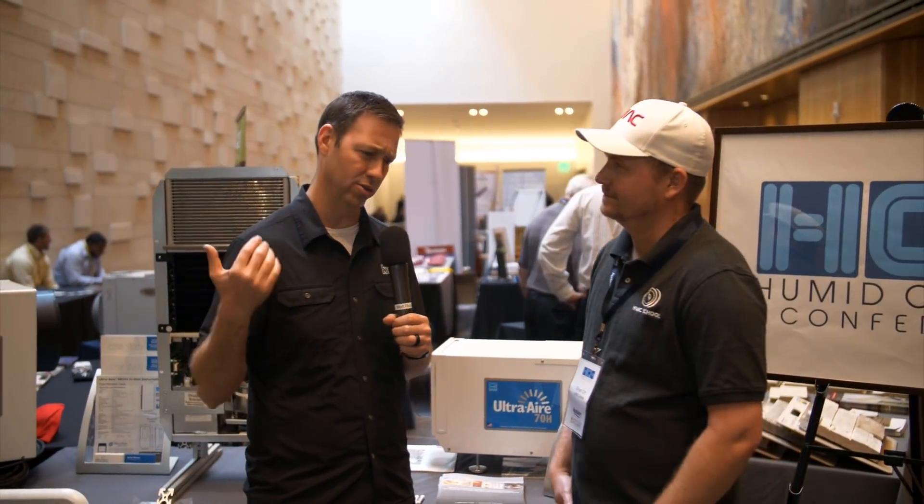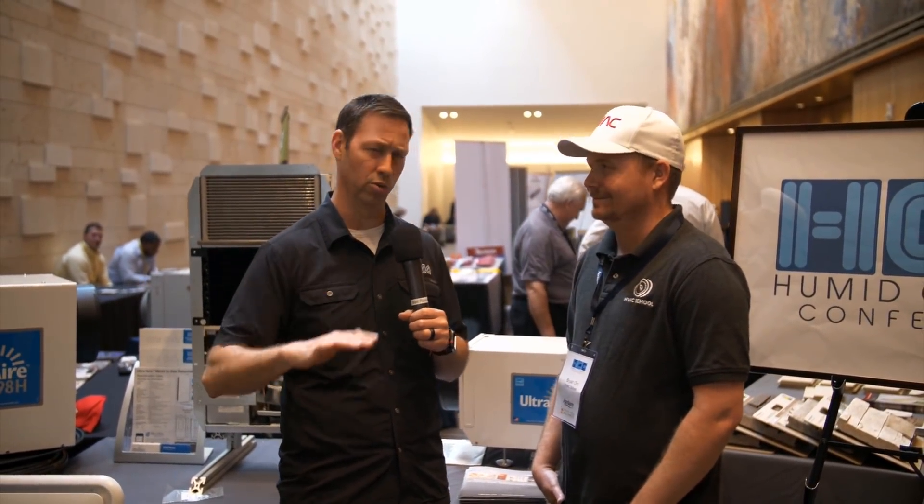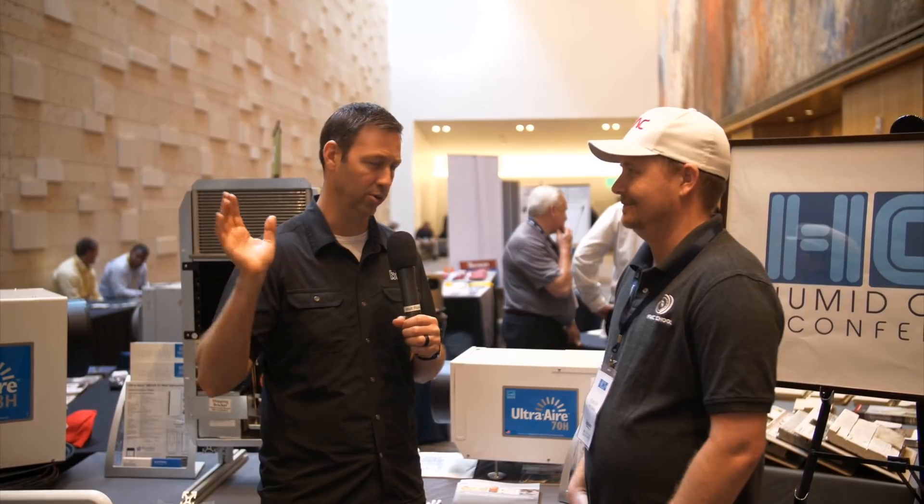Then I started having some higher humidity issues in houses. At the same time I started learning about VRF technology — variable refrigerant flow. The guys I was hearing from at conferences said, 'Oh yeah, this will totally control humidity, it'll run at these really low stages.' Compared to single-speed systems, these VRFs run down to 15%. I thought this is totally going to handle it — my compressor is going to run all the time, I'm going to be dehumidifying all day long, all in one box.